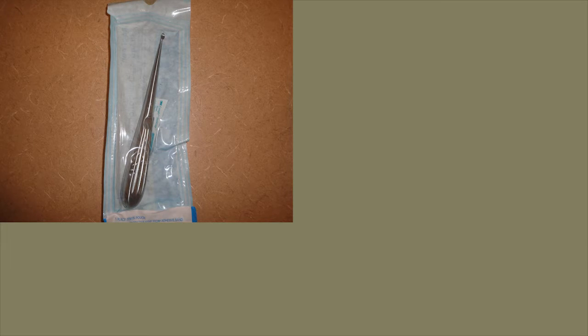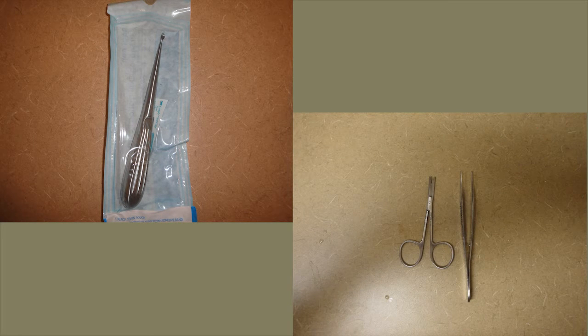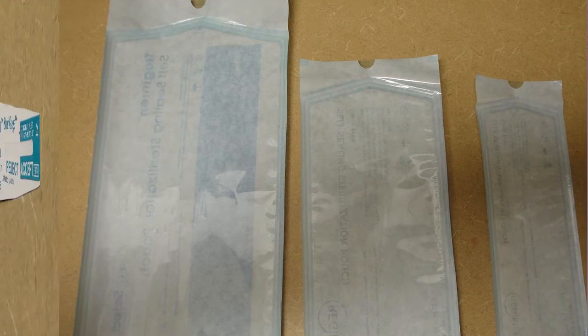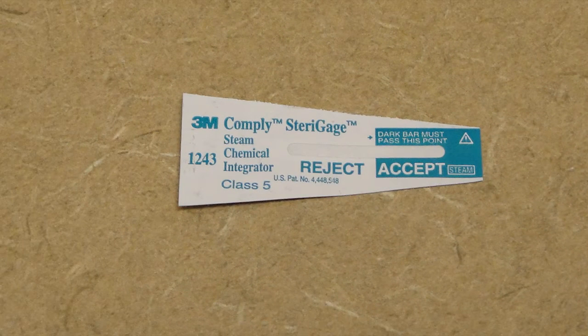In order to prepare individual instruments to be sterilized, and also suture removal kits, you will need to follow the same steps as the nail pack, except there are a variety of pouches in different sizes you can use. The idea is to minimize bulk, so choose the proper size for the instruments or instrument to wrap. For most individual instruments and suture kits, the long, narrow pouch will work perfect. You will need to remember to place a sterilization indicator in each pouch to ensure the instruments are sterilized. You will then place the pouches in the cassettes or in the tray to be sterilized.